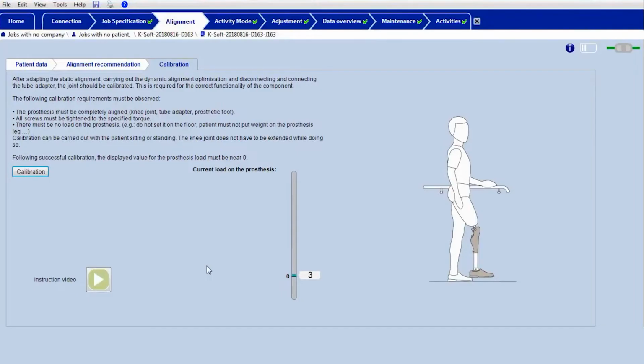Tightening the screws on the tube adapter alters the signals from the sensors. Therefore, the Kenevo must be recalibrated after each adjustment of these screws. As an example, this happens when the alignment is changed after checking measurements on the L.A.S.A.R. Posture or 3D L.A.S.A.R.